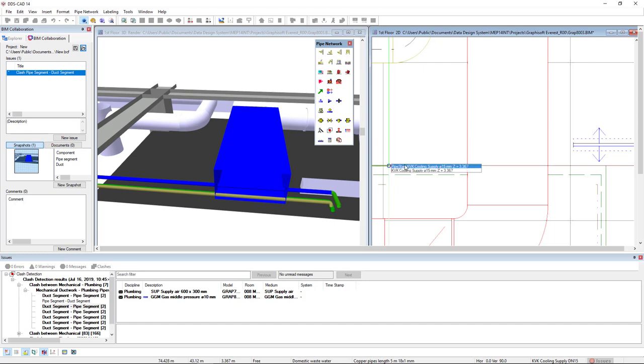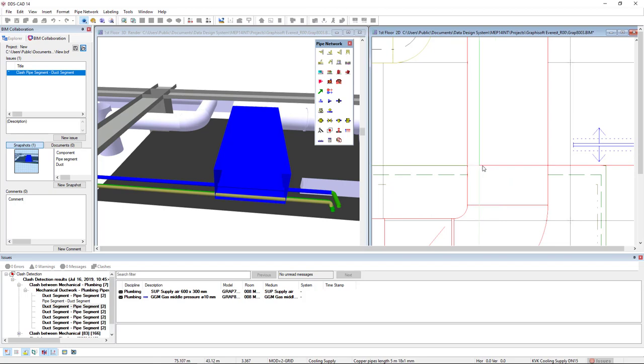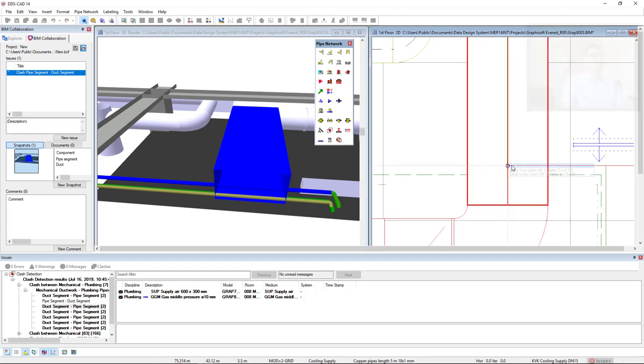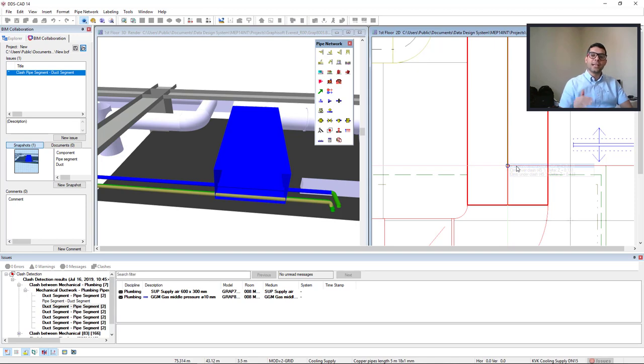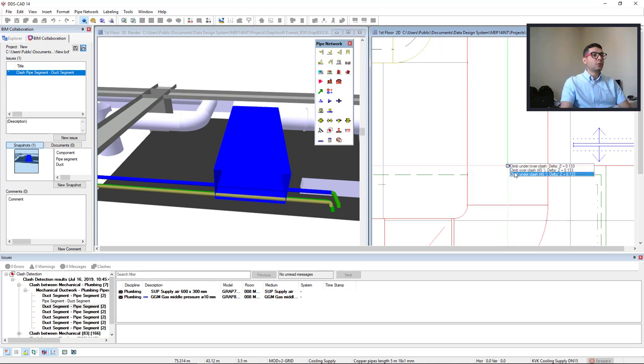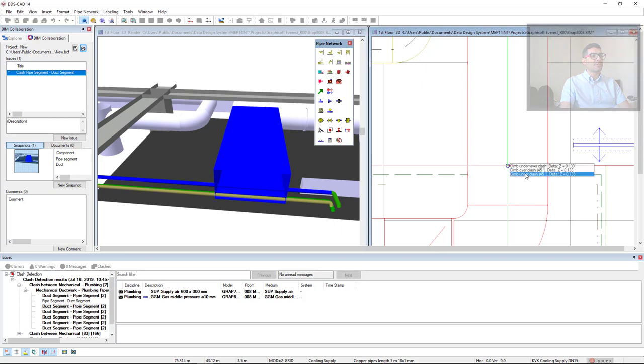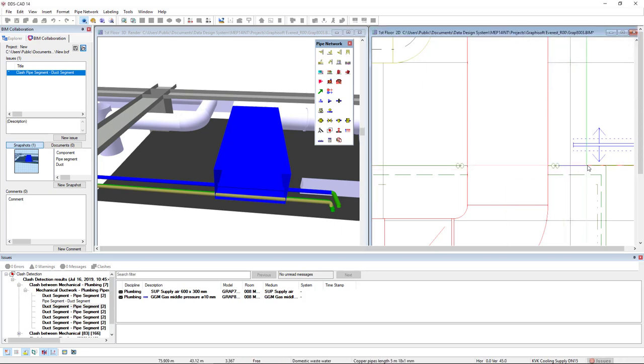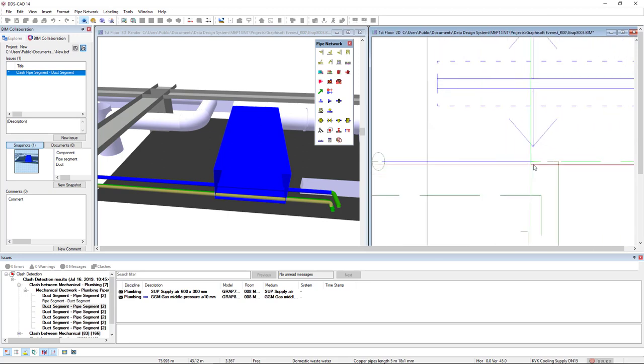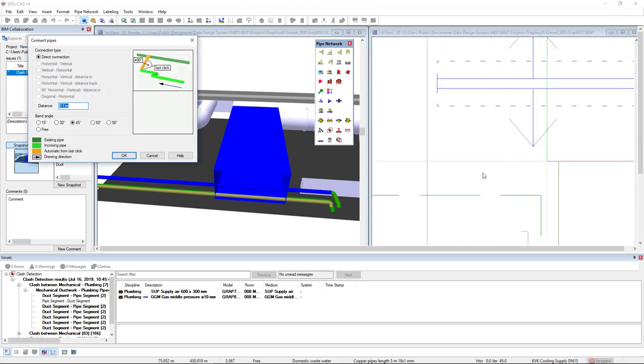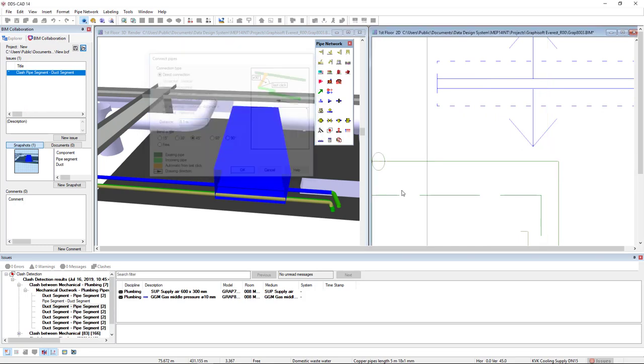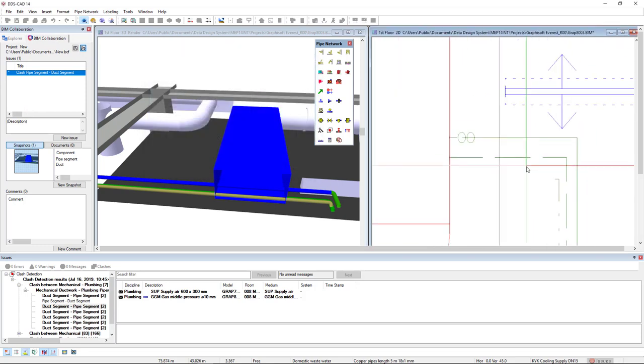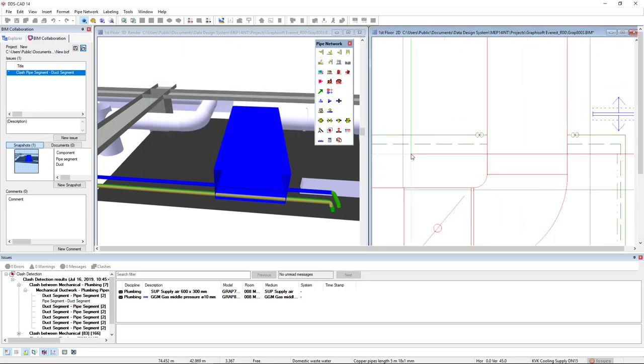So to the end of that pipe. If I move my cursor towards this duct, DDS-CAD indicates that this duct is in the same height of the pipe. So it indicates to me to make a climb over or climb under to avoid the clash. And I can connect to the end of the pipe system. The same thing I will do to the pipe below.